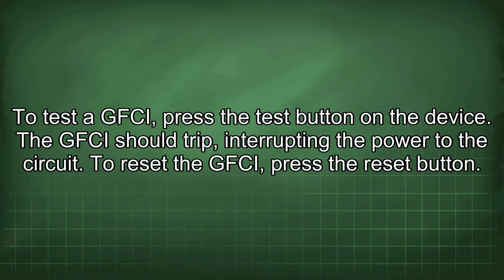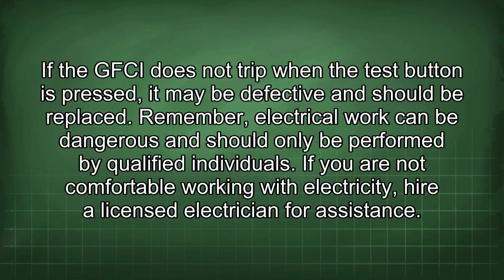To test a GFCI, press the test button on the device. The GFCI should trip, interrupting the power to the circuit. To reset the GFCI, press the reset button. If the GFCI does not trip when the test button is pressed, it may be defective and should be replaced.